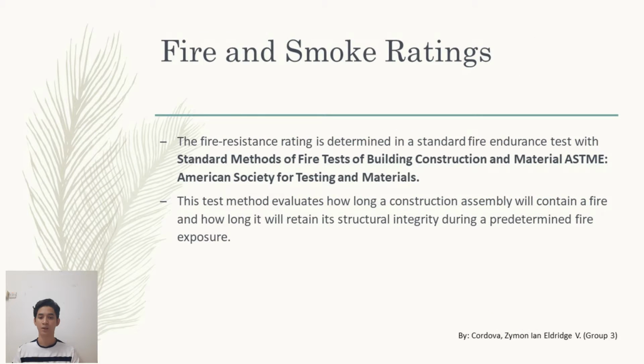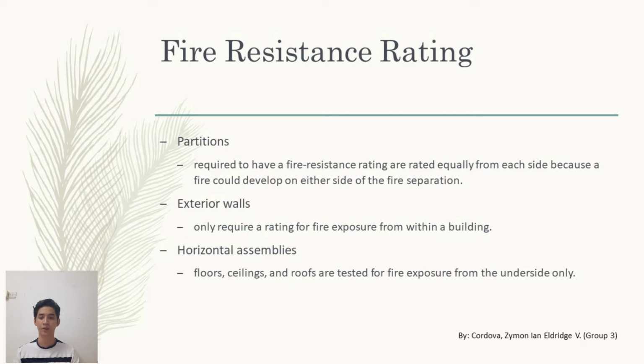The fire resistance rating is determined in the standard fire endurance test with standard methods of fire test of building construction and materials, ASTM, American Society for Testing and Materials. This method evaluates how long a construction assembly will contain a fire and how long it will retain its structural integrity during a predetermined fire exposure. Partitions required to have fire resistance ratings are rated equally from each side because a fire could develop on either side of the fire separation. Exterior walls only require a rating for fire exposure from within a building. Horizontal assemblies, floors, ceilings, and roofs are tested for fire exposure from the underside only.